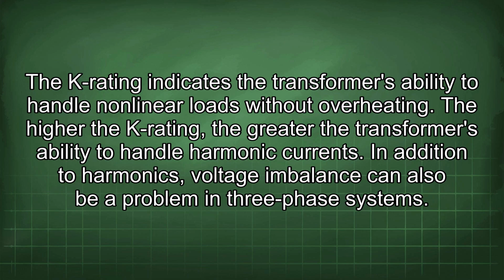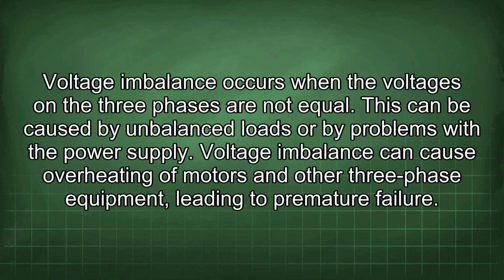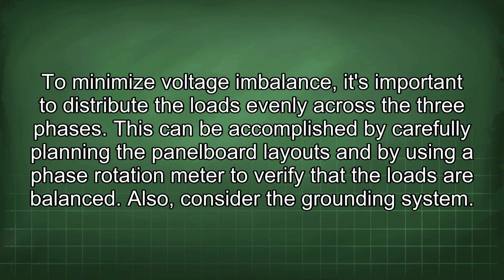In addition to harmonics, voltage imbalance can also be a problem in three-phase systems. Voltage imbalance occurs when the voltages in the three phases are not equal. This can be caused by unbalanced loads or by problems with the power supply. Voltage imbalance can cause overheating of motors and other three-phase equipment, leading to premature failure. To minimize voltage imbalance, it's important to distribute the loads evenly across the three phases. This can be accomplished by carefully planning the panel board layouts and by using a phase rotation meter to verify that the loads are balanced.